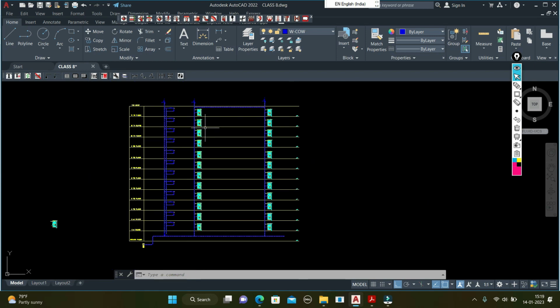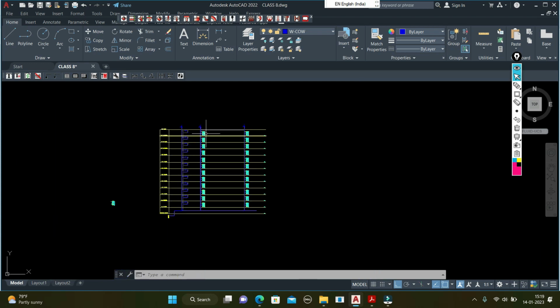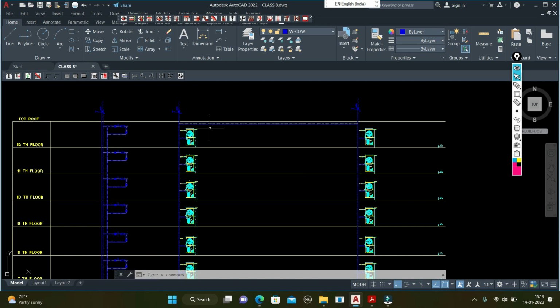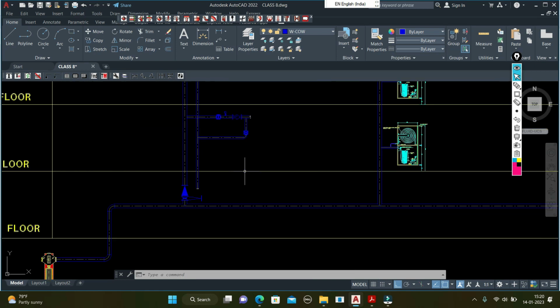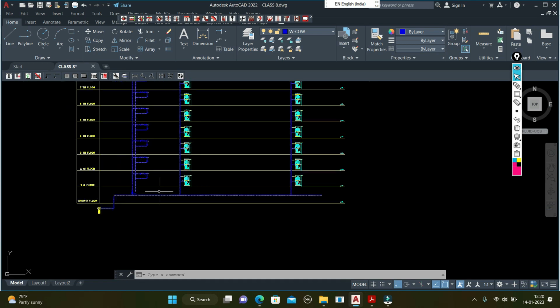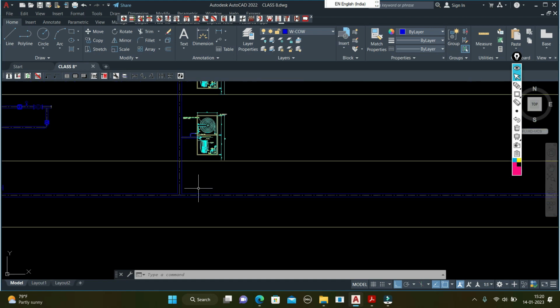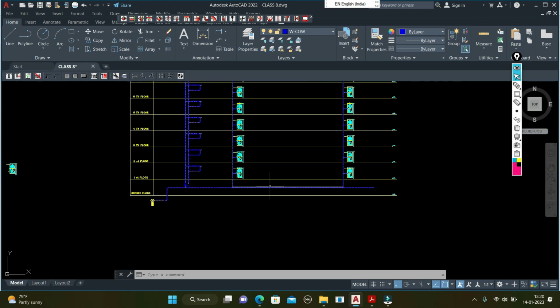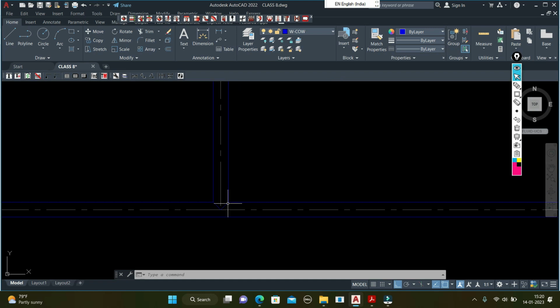Okay, and the wet riser, the standpipes in a mid-rise building. In low-rise building, no need to connect this one interconnected to header, okay, but in mid-rise building it's necessary as per the NFPA, okay. And this drain will go anywhere in a storage tank or a sump, okay. But here it should be the gate valve. Every header it should be a gate valve and drain valve, okay. So we place the gate valve here.